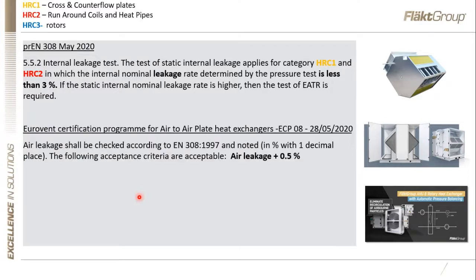If, however, you are a Eurovent certified manufacturer of air handling units, you then have to test an air handling unit with a plate heat exchanger in it, and the acceptance criteria for leakage within a standard air handling unit with a cross or counterflow plate heat exchanger, according to Eurovent, is 0.5%, not the 3% that would mean that you adhere to the EN standard.